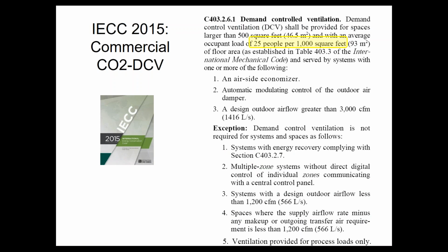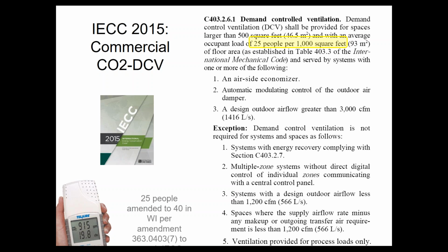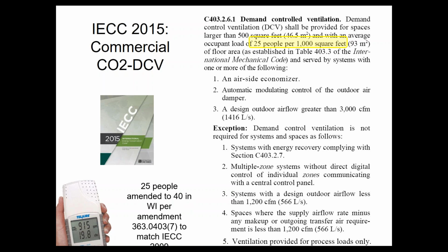For the 2015 code, if your project, if your area, your space, has a density of people of more than 25 per 1,000 square feet, then you will need to do demand control ventilation. There's some exceptions if you have smaller systems and things like that. But if you got like a high school auditorium or a gymnasium, or if you got a movie theater or these kind of places, you're probably going to have to do demand control ventilation. For you guys in Wisconsin, Wisconsin made an amendment to that. Instead of 25 people per 1,000 square foot, it's 40 people per 1,000 square foot. And that keeps it in sync with the old Wisconsin code, which was the 2009 version. Right? So keep that in mind if you're in Wisconsin. It's 40 instead of 25.